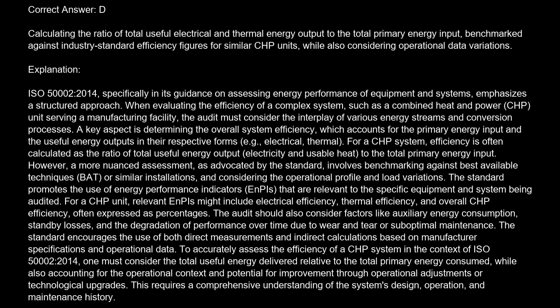The standard encourages the use of both direct measurements and indirect calculations based on manufacturer specifications and operational data. To accurately assess the efficiency of a CHP system in the context of ISO 50002:2014, one must consider the total useful energy delivered relative to the total primary energy consumed, while also accounting for the operational context and potential for improvement through operational adjustments or technological upgrades. This requires a comprehensive understanding of the system's design, operation, and maintenance history.